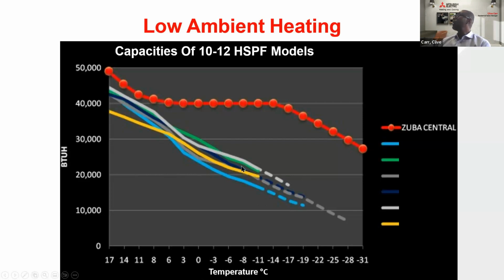So for a Canadian application, we need the heating capacity here at the lower temperatures. And you can see with a cold climate heat pump that it maintains the heating capacity, and the degradation of the heating capacity is at a lesser angle than your standard heat pump. You can see on a standard heat pump that it loses its capacity as the ambient temperature drops below 0. And it does so very sharply.